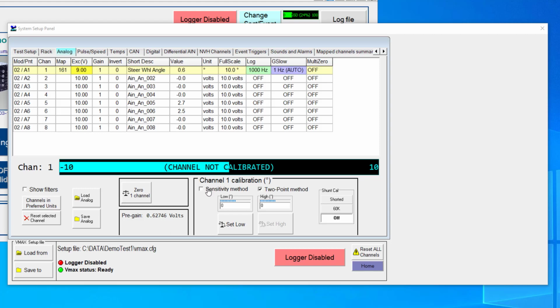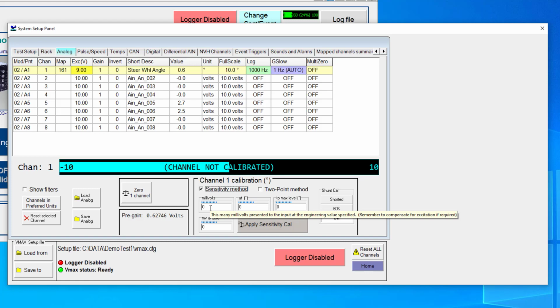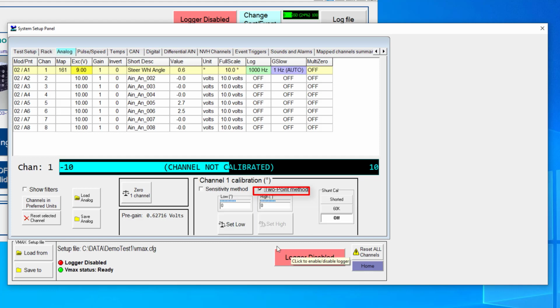In the lower part of the screen, you'll see that we have the ability to provide some sensitivity information. Typically, with a more high-end transducer, you would get a calibration sheet that might tell you that you have 50 millivolts per some engineering unit, and you could set a maximum level. I will show that later, but for this sensor, I'm going to calibrate it using our 2-point calibration method. With the 2-point calibration method, you just need to know 2 known values so that it can set up your slope of the line, and then you can zero the sensor externally if needed as well. In the case that I have here, I'm going to use minus 360 and plus 360 degrees, as this is a steering angle sensor.